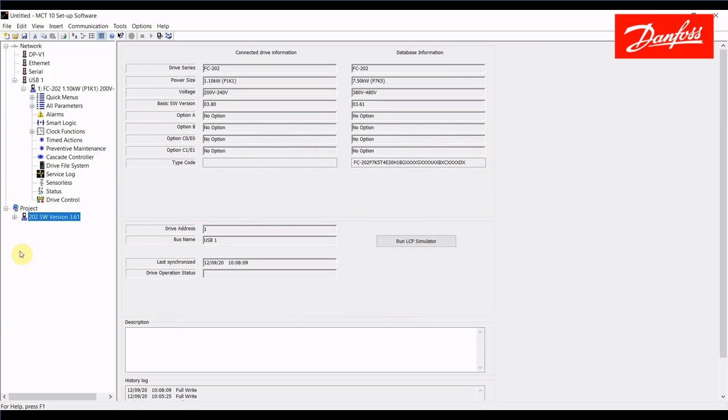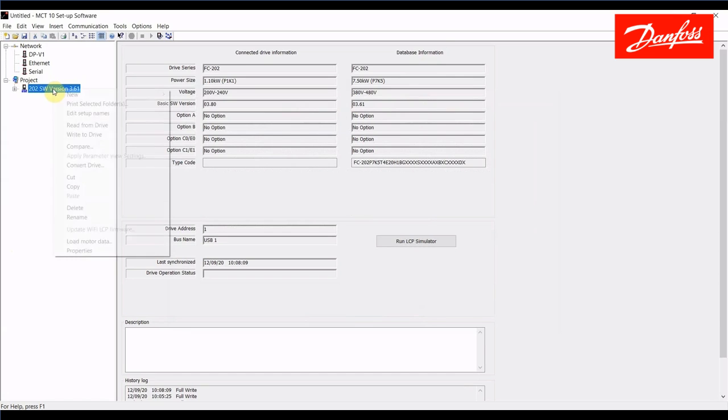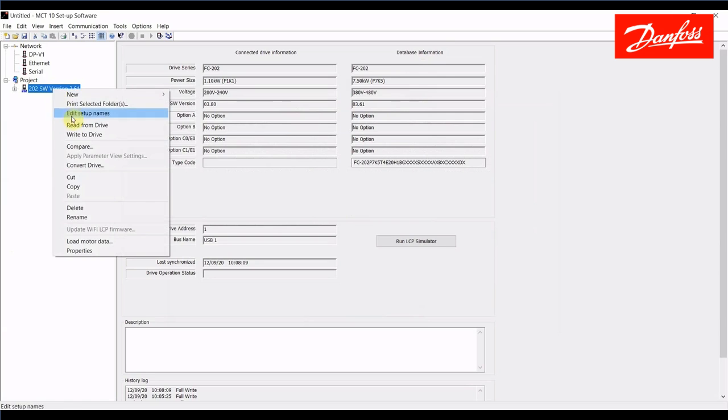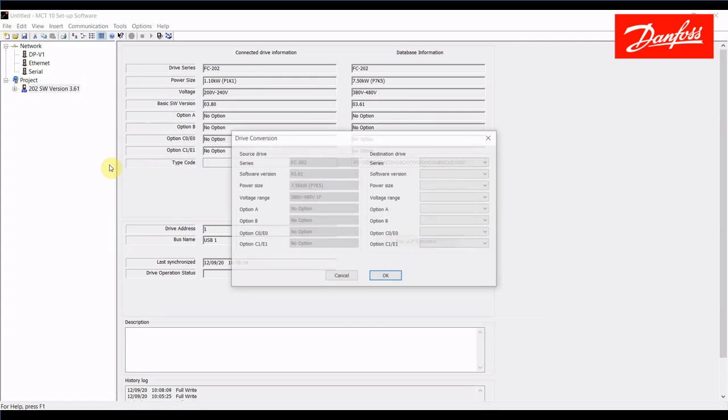So next thing I want to do is show you how to create a conversion table assuming you don't have a drive to connect to. So if I want to upgrade this project file that is based on software version 3.61, I can highlight that drive and I'm going to select convert drive. Now before I get into this I should mention to you that you have to be logged in or running MCT10 in administrator mode in order to prevent Windows from blocking these functions to work properly. So to do that you can normally right click on the program icon and select run as administrator. Once you've done that you can go in here to the convert drive tool.